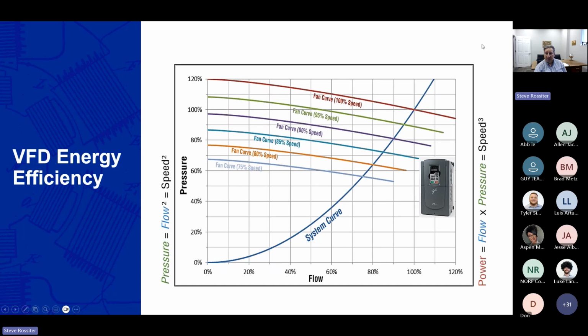So the affinity laws would apply to centrifugal fans and centrifugal pumps, where your flow and your pressure and your speed all have different relationships. So if I take this fan curve and look right here at 100% flow and 100% pressure, and this could be as well, could be a pump, and there's where my curve is going to start. That's going to be 100% speed also. Now, if I reduce that, if I come down that curve and reduce the speed to 80% speed, I still have 80% flow because flow is proportional to speed. My pressure, on the other hand, is down to around 62 or 63%.